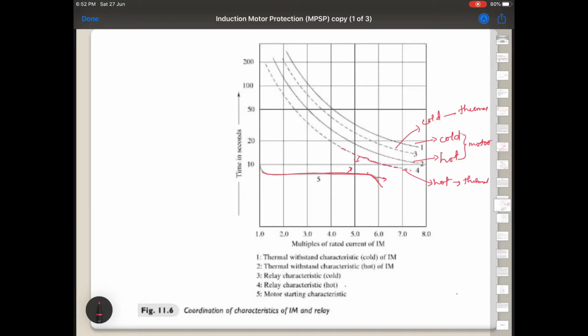That problem comes only when you are starting the motor in hot condition, meaning you have already run the motor and stopped it for some time, but the motor is still heated up, and you are starting the motor with some temperature in it and with a heavy load. In that case, you cannot use your conventional thermal relay. You will have to go for a microprocessor or DSP based induction motor protection.